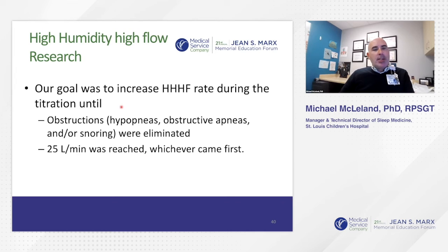Our goal was to increase high flow at the rate during the titration until obstructions, hypopneas, obstructive apneas, and/or snoring were eliminated. The maximum we would go to was 25 liters per minute if we had to reach that, or if we got rid of the obstructions first, whichever came first.